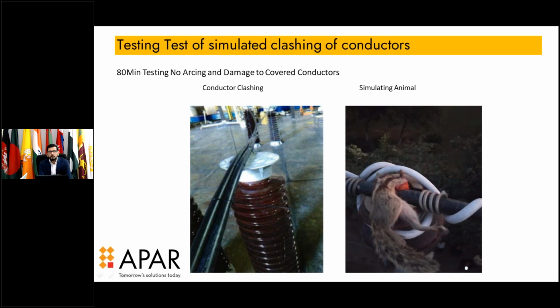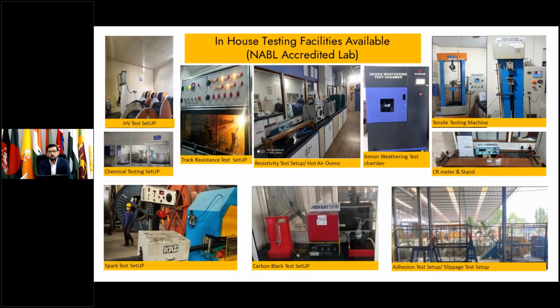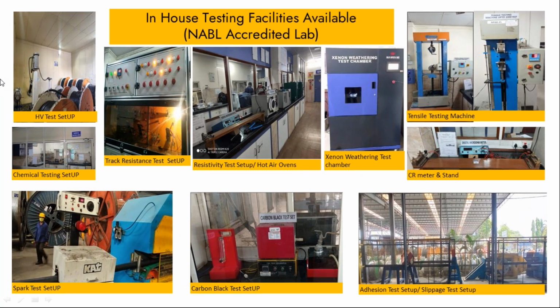So what a lab should have: any manufacturer should have a lab which can provide all the tests as per the EN standards, with an HV test setup, then chemical testing setups, then the most important track resistance test setups, then resistivity tests, hot ovens, xenon weathering test chambers, tensile testing, CR meters, then spark test, carbon black test, and then the conductor slippage test. All fixtures for the slippage test should be there, because while doing the triple extrusion of the cable, the slippage test will show that the conductor will not come out or slip out from the insulation part. So those tests are very important. These are already elaborated in the EN standards, so that has to be taken into consideration thoroughly.